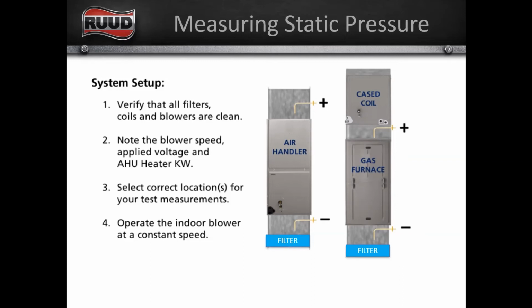One of the questions was on a ducted return, when is negative extreme? My response was that most manufacturers design for a total static pressure of 0.5. So that 0.5 has to be divided between your supply and return. But we really don't want to go above a 0.5 total static pressure.